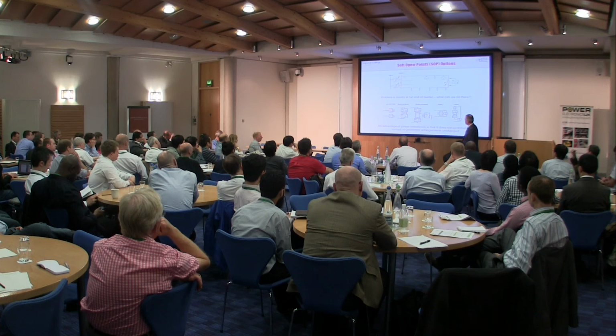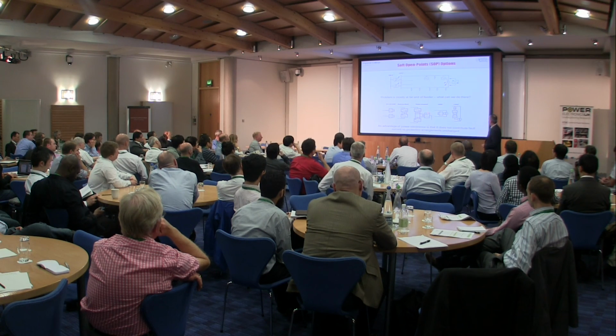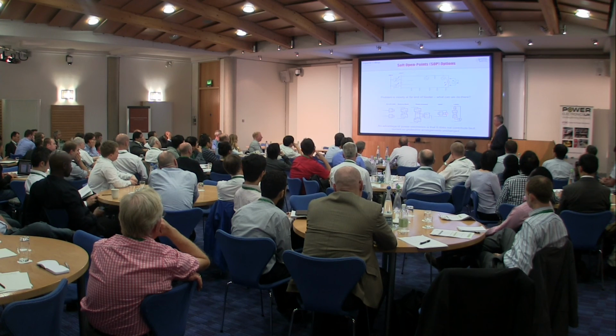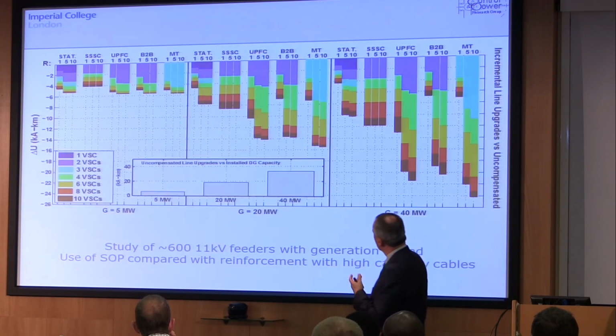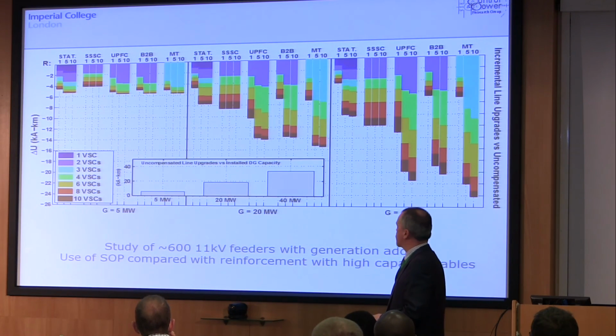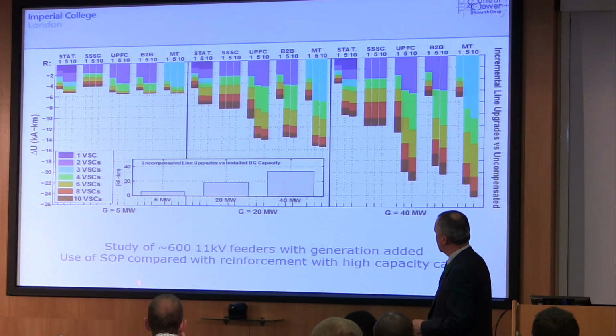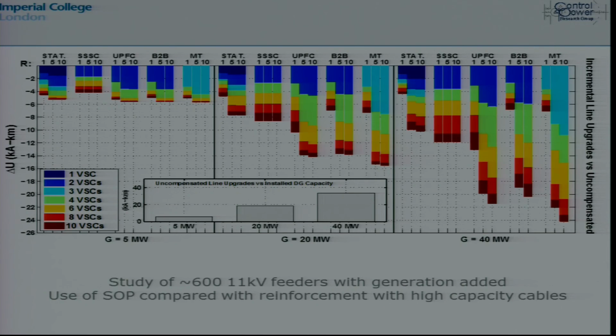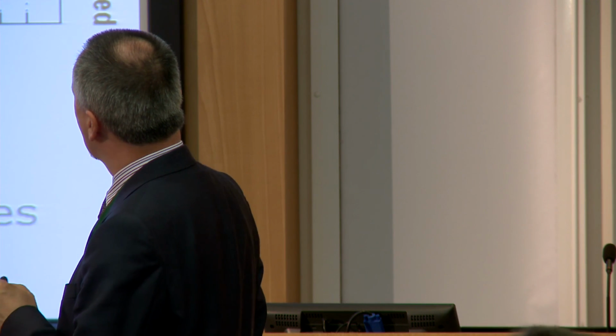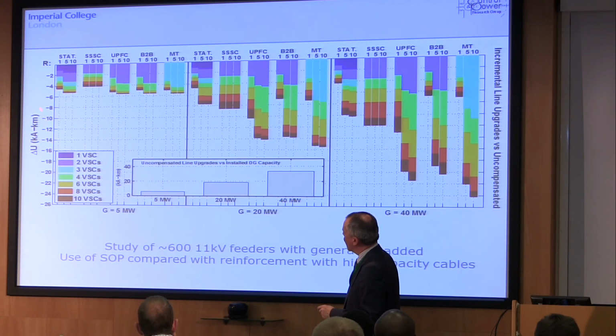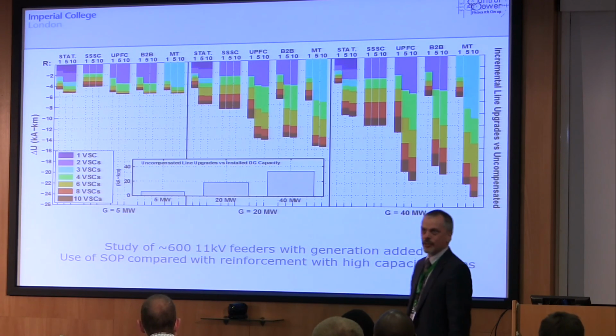I could attempt to do that with StatComs independently on the two feeders. I could do it in a multi-terminal arrangement. I could do it with a series-connected converter, which might be quite nice if that can be a partially rated converter, or a series shunt, sort of UPFC, Unified Power Flow Controller arrangement. So we've done a bit of work looking at that, trying to quantify the benefits. So this was a study of around about 600 11 kV feeders across southeast England, grouping them into substation groups of 6 or 8 feeders, and then placing power converters in several formats as StatComs or back-to-back converters, and at different ratings, and looking at what it did in terms of saving on line upgrades. This is kiloamp kilometers of saved reinforcement.